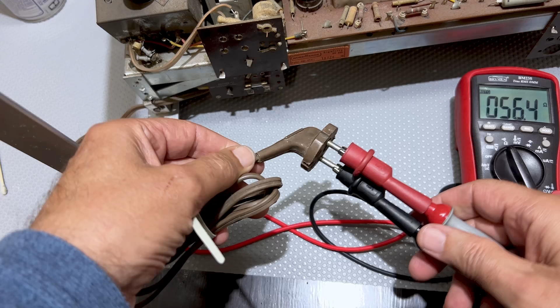Yep, it's consistent. So what we've done is we've actually checked continuity between this point and that point on the mains plug, and it's going through the fuse, through the switch, through the primary, and we're getting more or less what we expect. This is going to be a few ohms off because of dirt that might be on the plug, some still on the fuse holder, some on the actual switch.